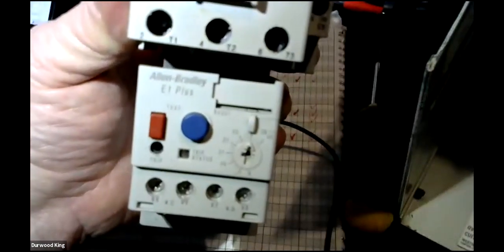Say it again. We don't want that. No. So the calculations we went over at 125 or worst case 140%, it's what you want to do with this, and size your wire accordingly. Boost your wire size accordingly, whatever you set it to, so that you're not going to have a fire hazard or personnel hazard, somebody getting hurt.